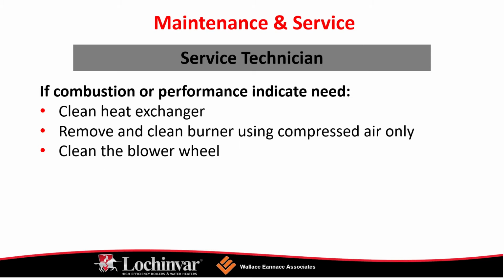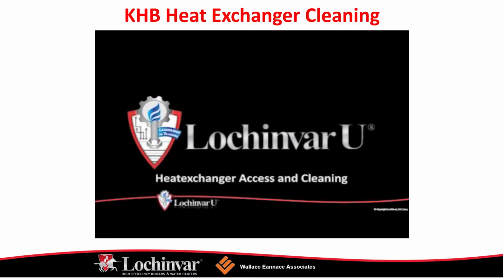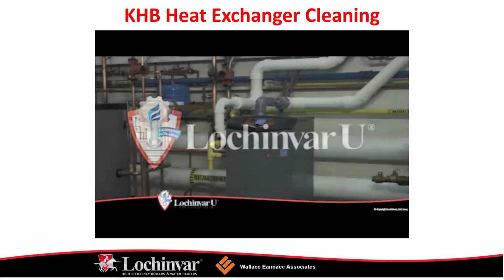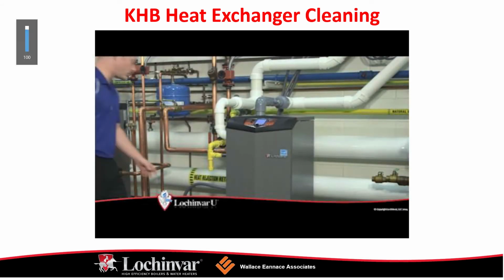Okay, so we're back from break. Maintenance and service is what we're under here, and basically the service technician in general can expect to certainly check wiring and connections, perform startup checkout, and performance verification. We want to make sure our flame is stable and uniform. We want to make sure we see at least 10 microamps at high fire on the flame signal. And we want to clean the heat exchanger if flue temperatures are more than 54 degrees above your return water temperature.